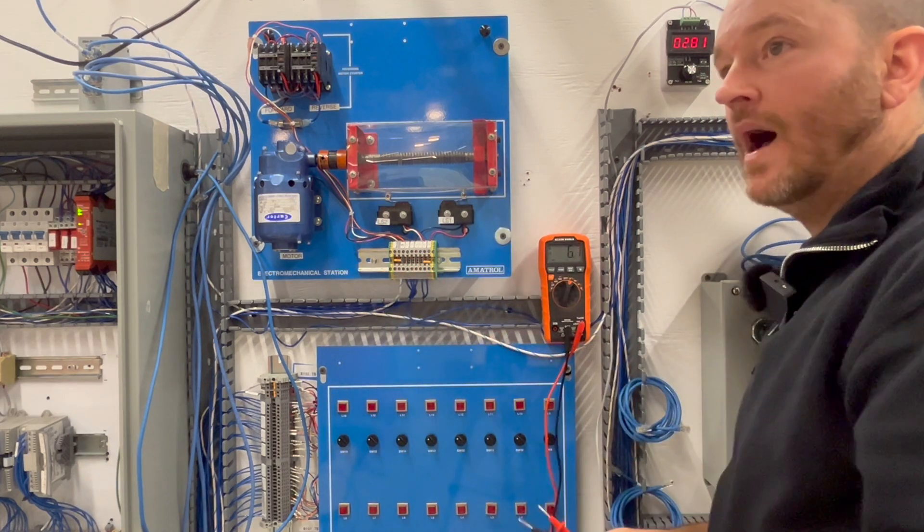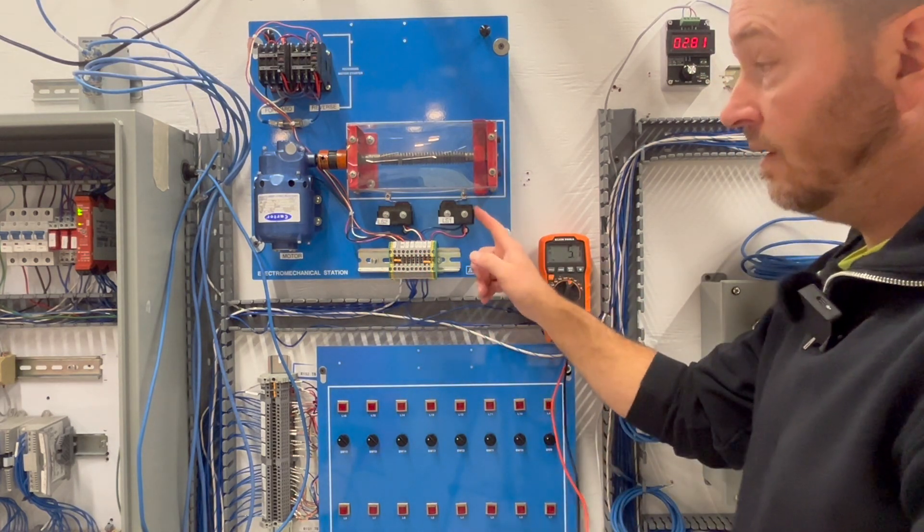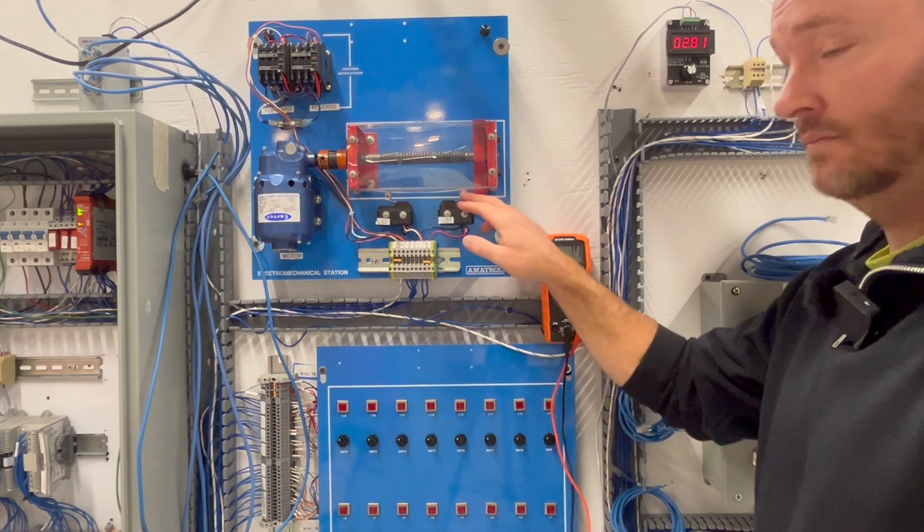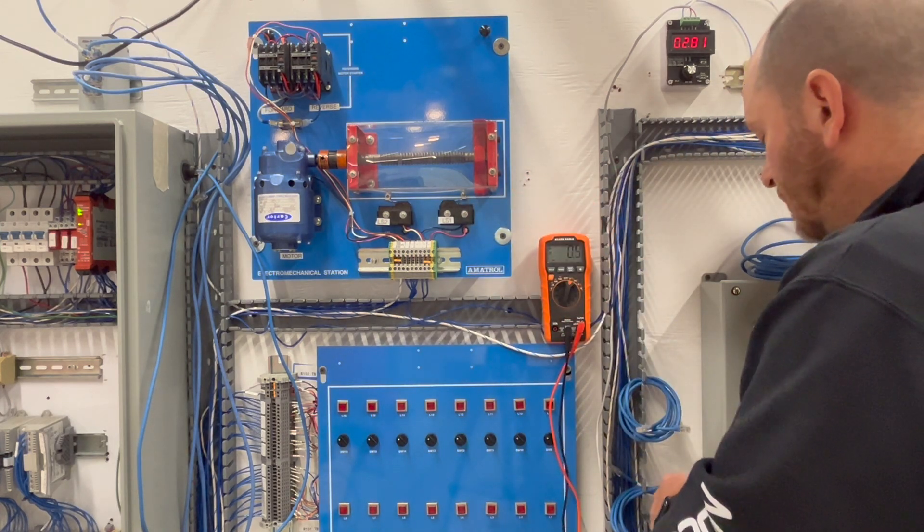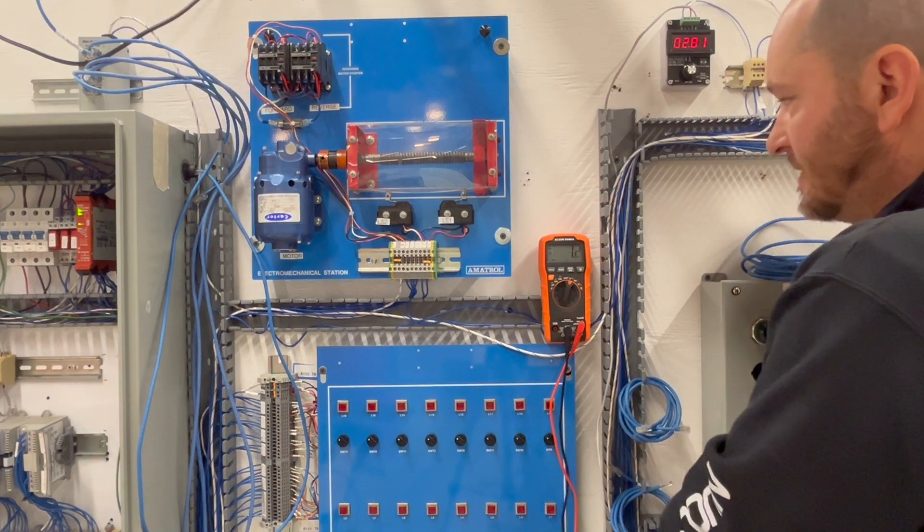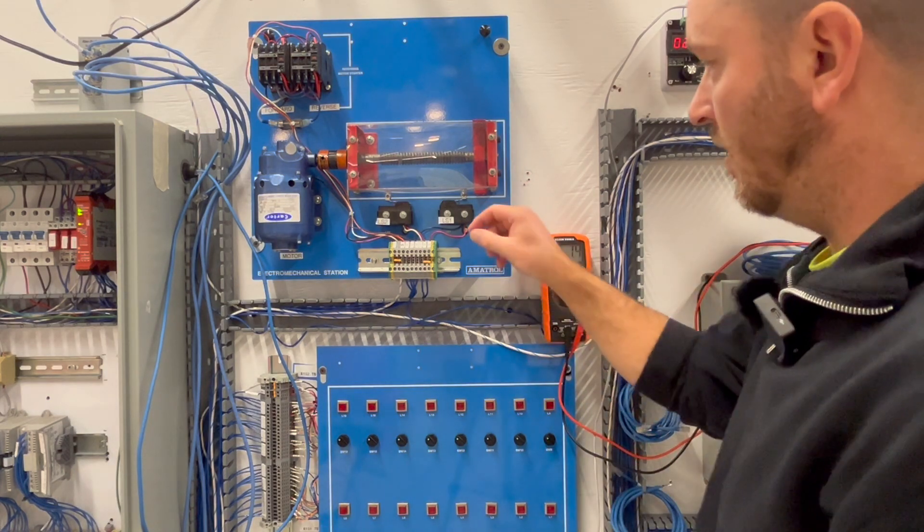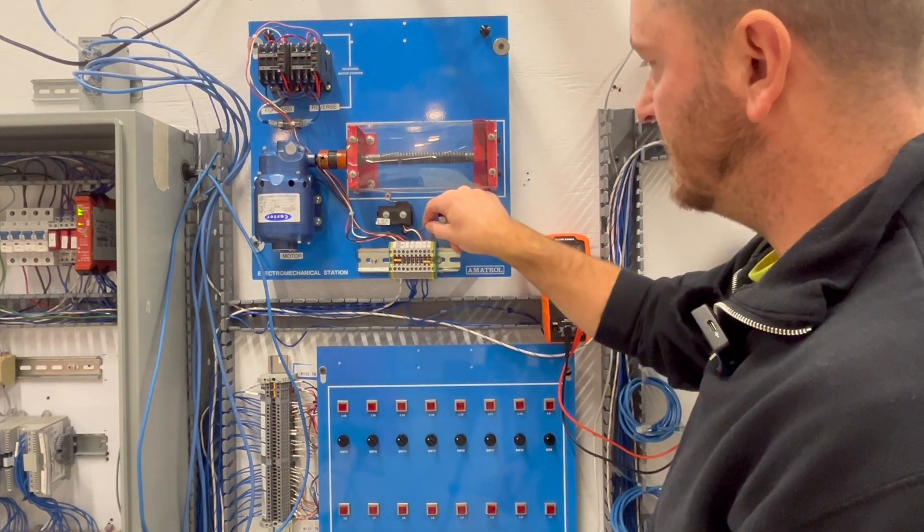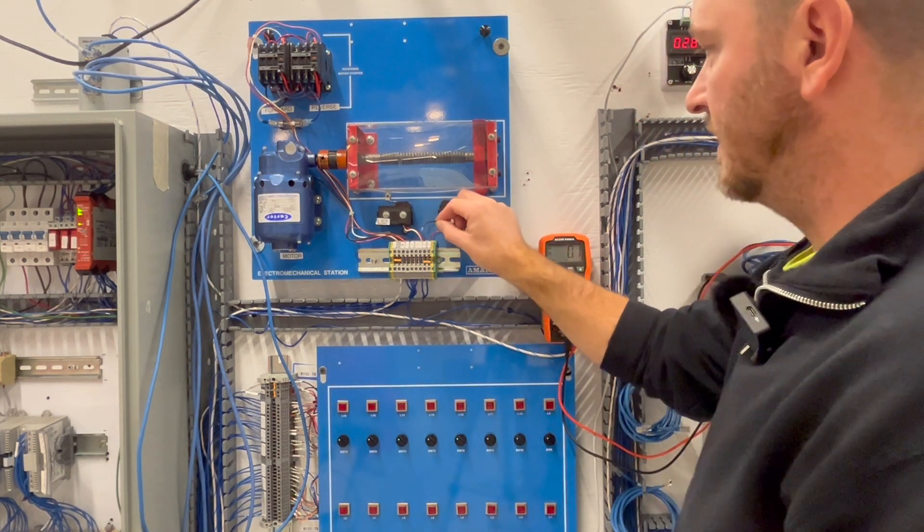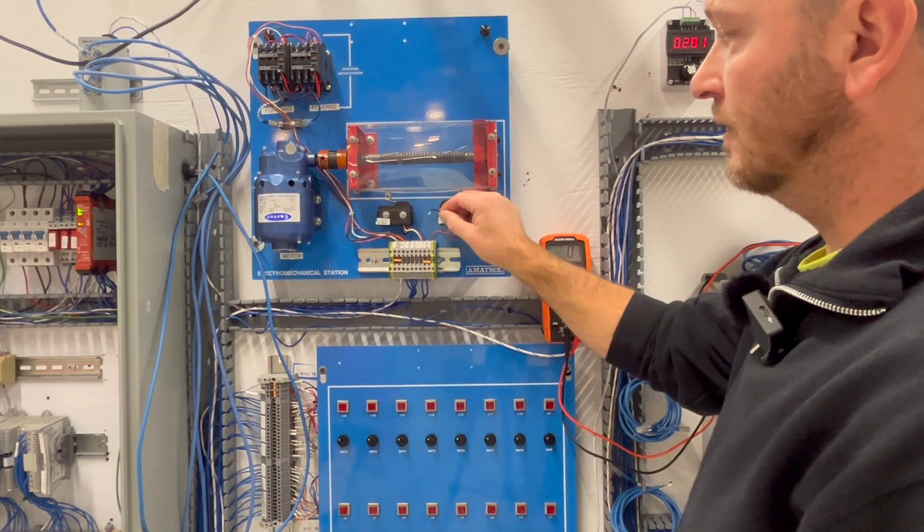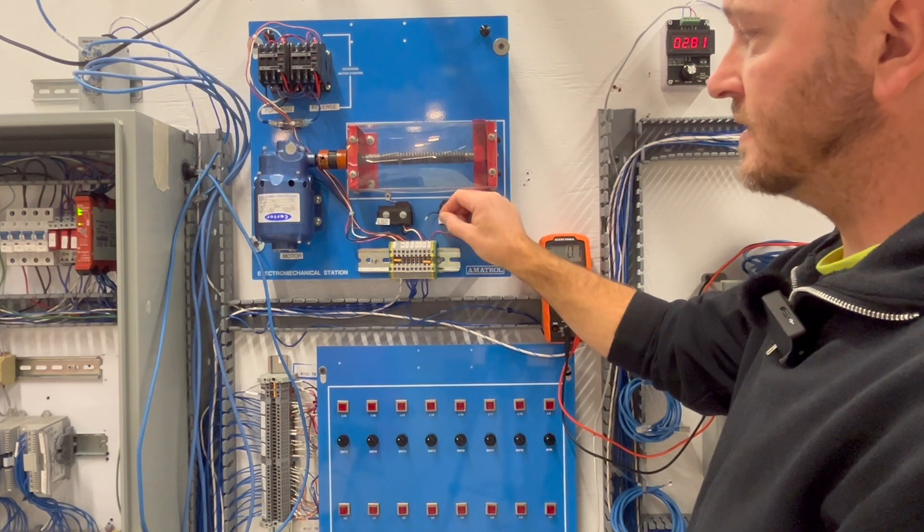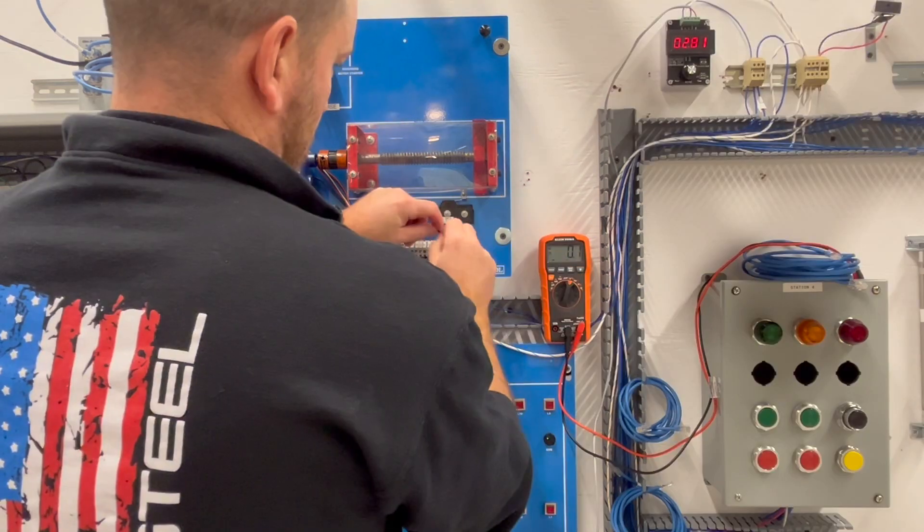Okay so now there are two possibilities: one, the switch has gone bad, that can happen, or what I would probably also start to do is a little tug test to see what's going on. Okay so I know that's here I trace this down, oh and look at this it was hidden behind there I couldn't see, I had a loose wire. So what I'm going to do is I'll come in here, fix this and see if that solves the problem.